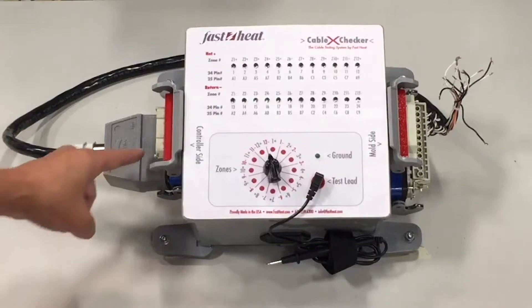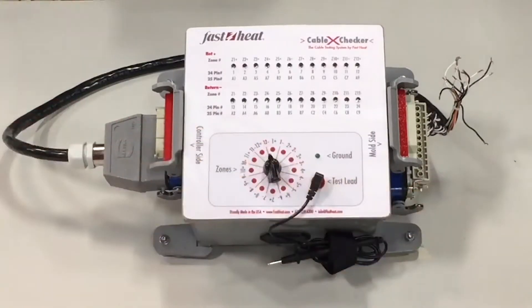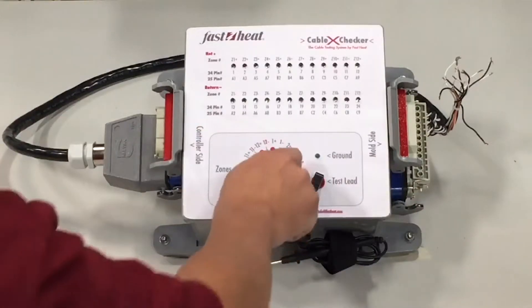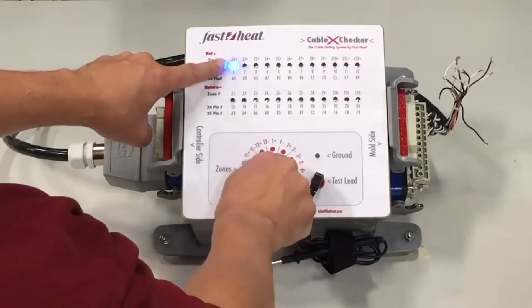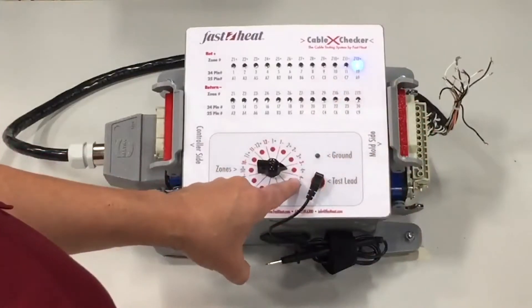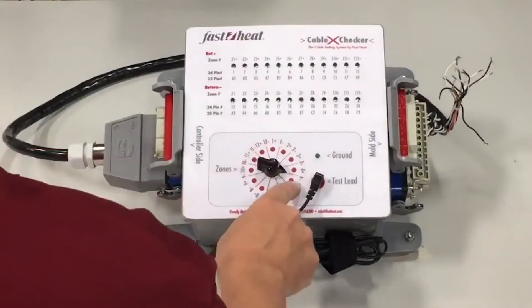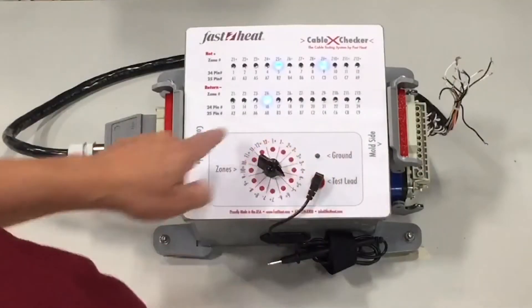Select a cable to test and plug the corresponding ends into the connectors on your Cable X Checker. Then cycle through your zones using the dial. You can quickly determine continuity, miswired zones, opens, and shorts.